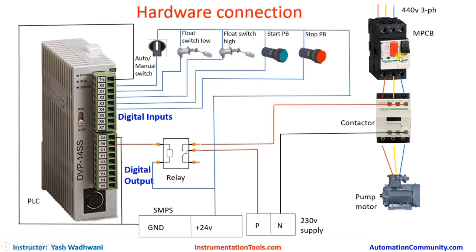Our main output is the pump, but to run the pump we require a starter. This is a DOL starter with an MPCB and contactor. We cannot energize the contactor directly with the PLC, so we have to use a relay. First, we connect the ground of the SMPS to the common of the digital outputs, and digital output Y0 we connect to one terminal of the relay.